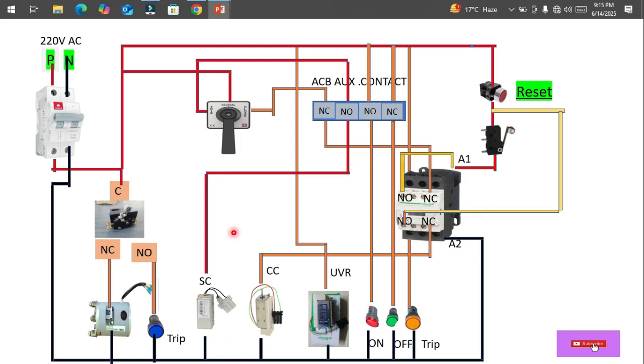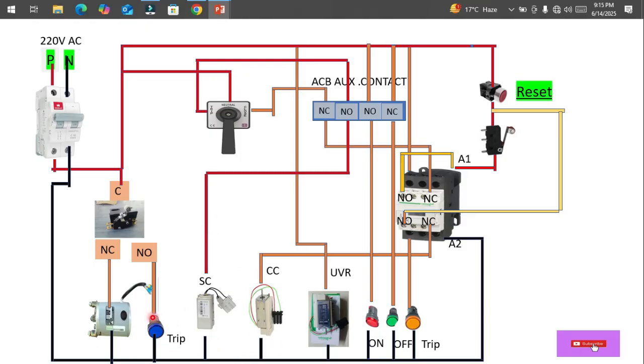The power then reaches the shunt coil. When phase reaches this coil and neutral is connected from the other side, the coil gets activated and it pushes the plunger toward the contact, which finally trips the circuit. In case of a fault, the micro-logic controller display will give a command to the shunt coil as well, and it will trip the breaker.